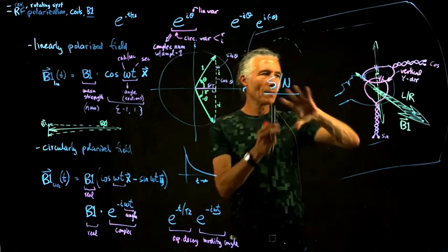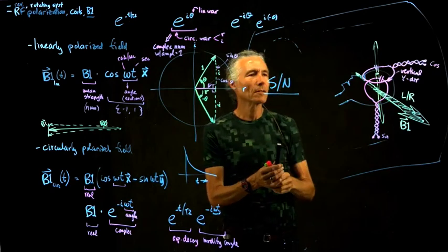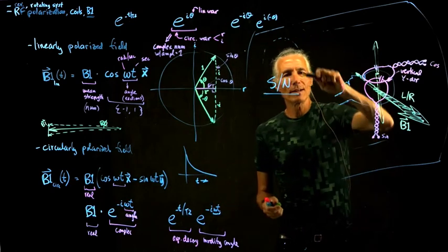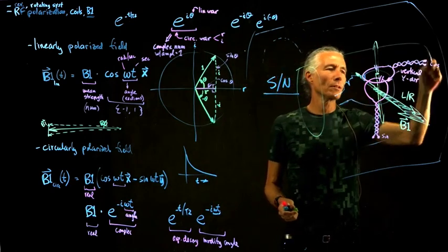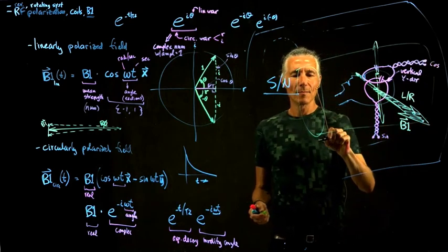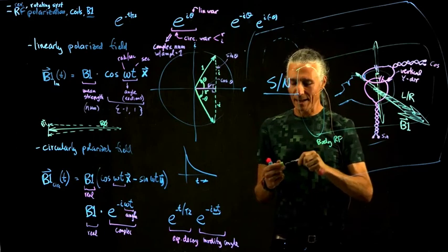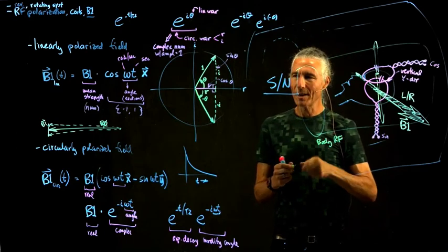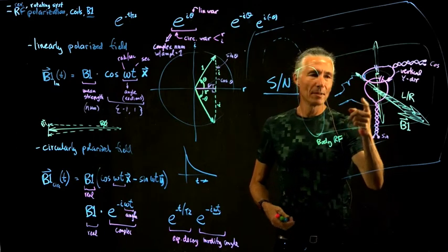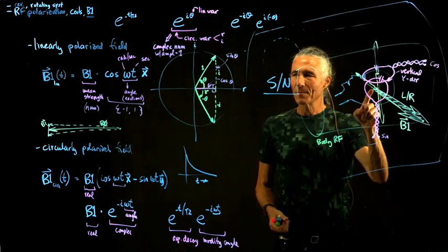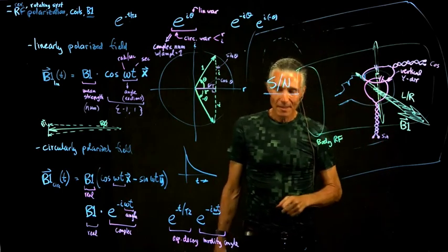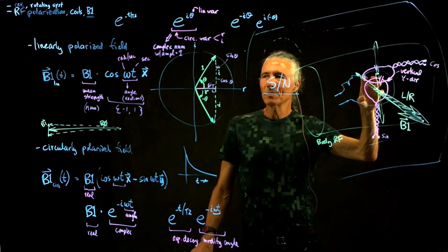And in fact, you've got a body coil in there. Remember, there's the body coil that you use to transmit, which is a really big coil in there, body RF. And that coil, that's a big antenna. And that's a great antenna, and it would actually pick up just fine. So that's not the reason why small coils have a better signal to noise.